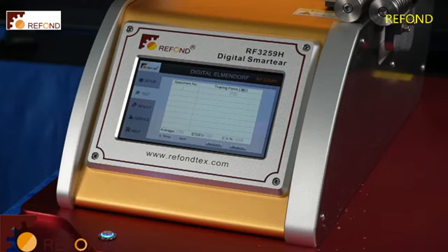Metrology-speaking, they can only measure the cutting size, the distance between the clamping faces. But for the test result, there is no metrology standard or procedure. So for third parties, there is currently no way to do a metrology calibration of the result, not like using a weight or something. They only have a metrology standard for the older, fully mechanical Elmendorf. For the digital one, there is none.